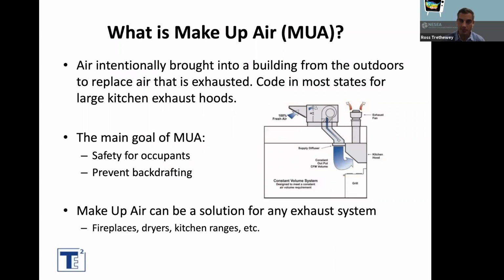So what happens when you have a very tight building and you're exhausting a lot of air through it? You run into a problem. How do you solve it? That's called makeup air. I would define it as air intentionally brought into the building from outside. That's basically going to replace the air that's exhausted, and it's going to be code in a lot of areas across the United States. What we're trying to do is deliver safety and prevent backdrafting of appliances. We want to make sure the air quality is nice and healthy, and we don't have backdrafting of fireplaces, gas, oil, any type of furnace or boiler, any kind of combustion device that's not sealed combustion is at risk for backdrafting. Dryers are a common one as well. So, next slide.